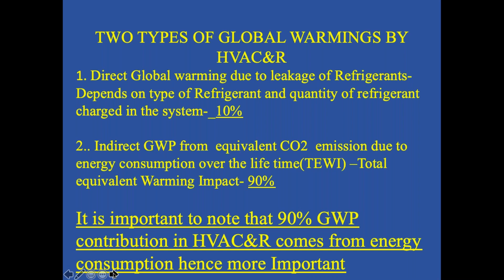The indirect global warming, known as TEWI effect - total equivalent warming impact - is 90% because of the energy consumption of a refrigeration plant. So it is important to note that 90% of global warming is from energy consumption, and hence we need to concentrate more on energy consumption by the refrigerants besides leakage of refrigerants, which contributes only 10% global warming.